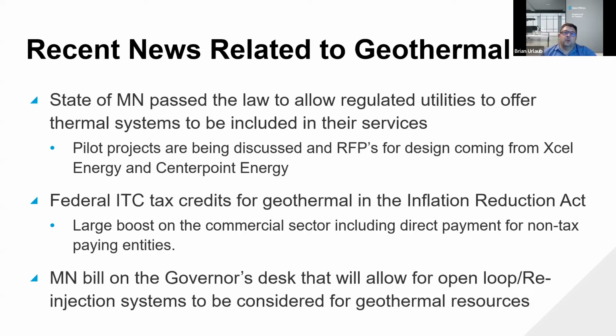But there's a technology where, if done correctly and the water is good and readily available and there's enough, you can pump out of an aquifer, go through a heat exchanger, thermally exchange, but don't do anything to the water, and put it back into the same aquifer. As long as it goes back to the same aquifer, you're just changing thermal energy, you don't do anything to that water, and it stays within that aquifer. We've got a lot of hydrogeologists on our team, and this has been happening in a lot of different places in Ontario and out east, and it works very well. It has to be the right scenario, the chemistry and everything has to be right.